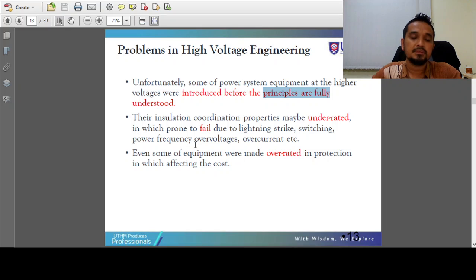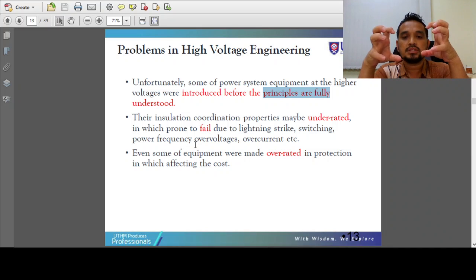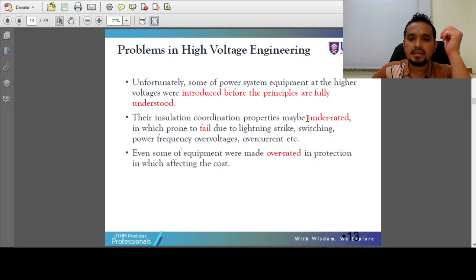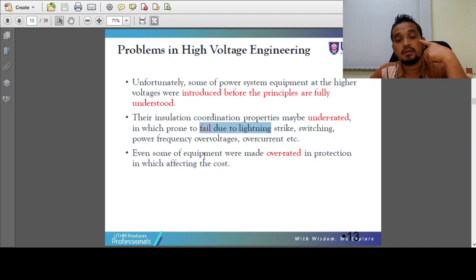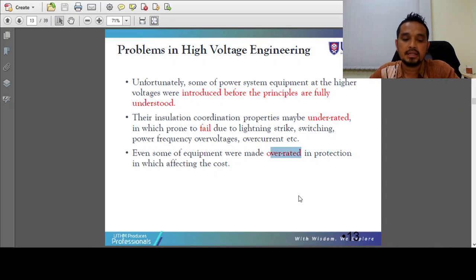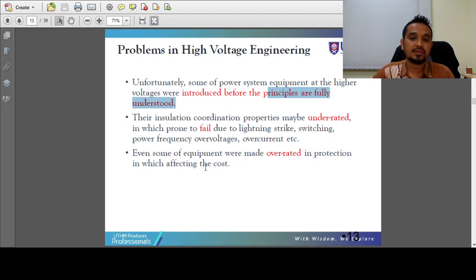What does that mean? It means we developed power system equipment without good insulation coordination — equipment that was underrated and could easily fail due to lightning strikes, switching, and so on. Some high voltage equipment was overrated, which caused financial damage and costing to the manufacturer. So the balance between underrated and overrated was still not achieved, because some fundamental knowledge was not fully discovered.